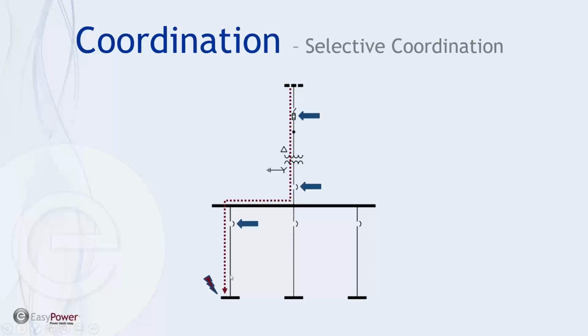So ideally, realistically, any one of these breakers or protective devices should trip at some point. The goal is to make sure that this feeder breaker trips first, thereby preventing the loss of energy or control to the rest of the operations. For instance, if we lost the primary fuse and the whole plant goes down because of a simple fault at a small motor, it would be onerous as far as the amount of lost productivity for something that could have been avoided.